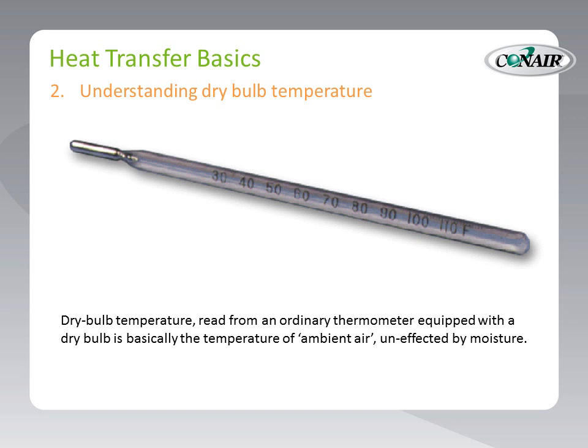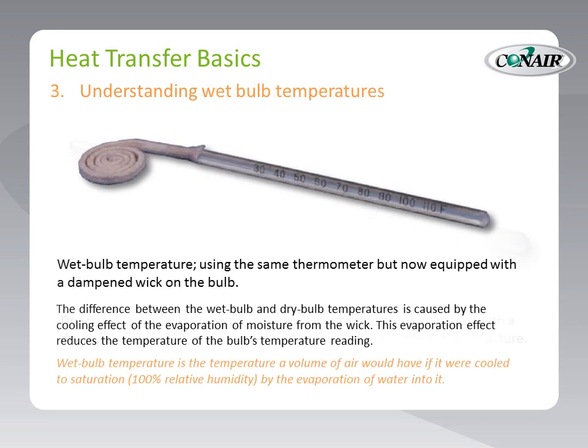We will also need to understand both dry bulb and wet bulb temperatures. Dry bulb temperature, as the name suggests, is measured with a thermometer that has a dry bulb and represents the ambient temperature without any evaporation influence. Wet bulb temperature, also as the name suggests, is measured with a bulb of the thermometer covered in a dampened wick. As the water evaporates from the wick, the latent energy required for that evaporation cools the thermometer bulb. The difference between dry and wet bulb temperatures represents the ability of the ambient air to accept additional moisture. The wider the gap between dry and wet bulb temperatures, the more moisture the air has the ability to accept.